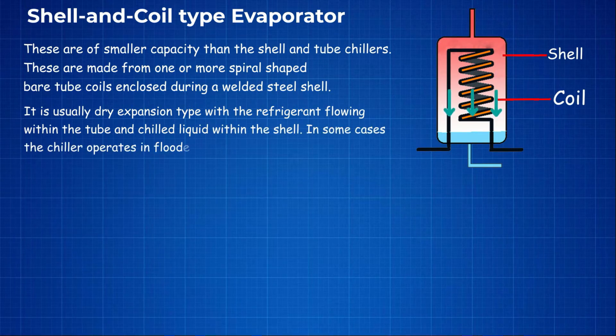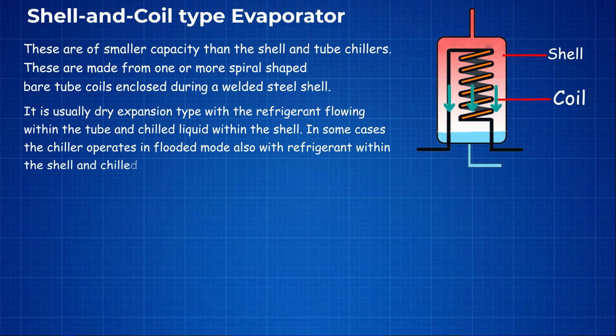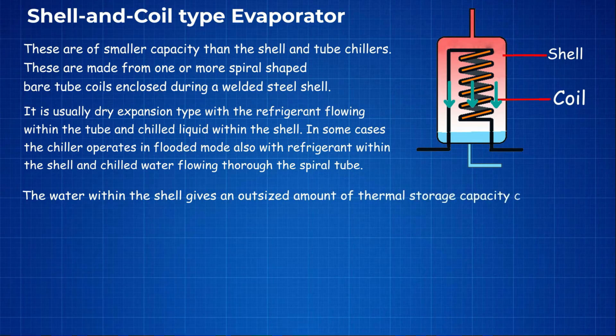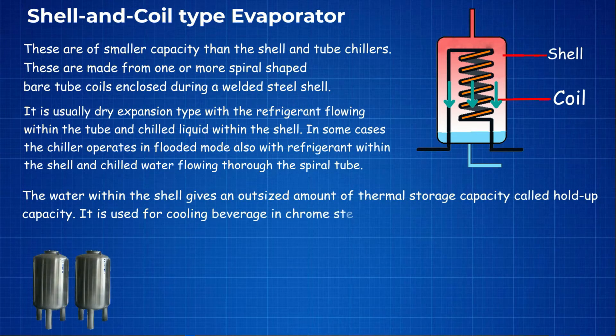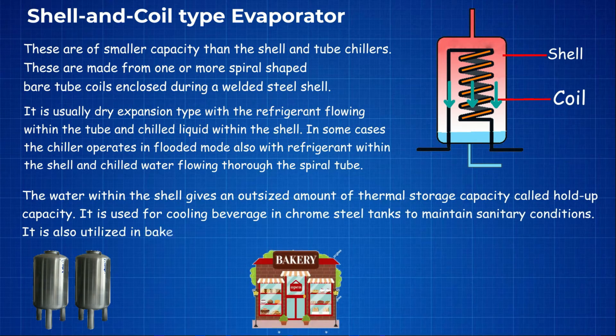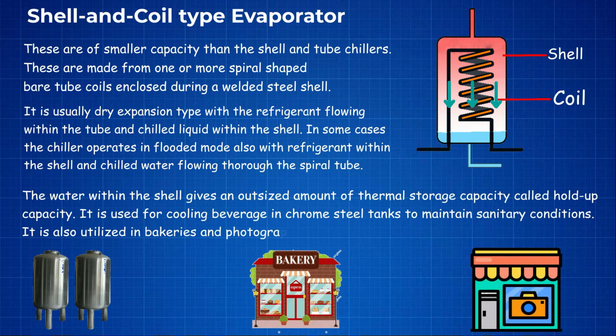In some cases the chiller operates in flooded mode also, with refrigerant within the shell and chilled water flowing through the spiral tube. The water within the shell gives an outsized amount of thermal storage capacity called holdup capacity. It is used for cooling beverages in stainless steel tanks to maintain sanitary conditions, and is also utilized in bakeries and photographic laboratories.